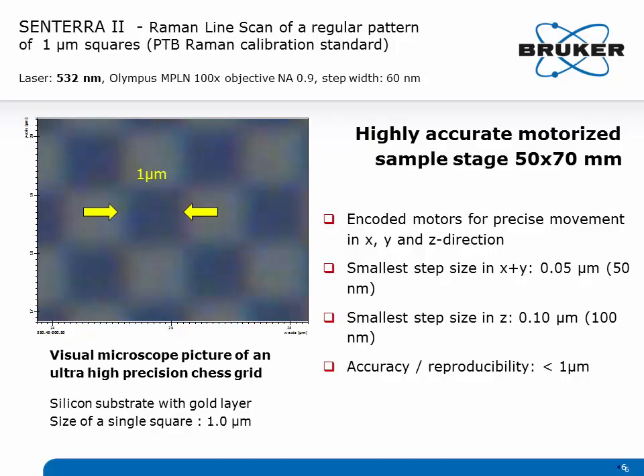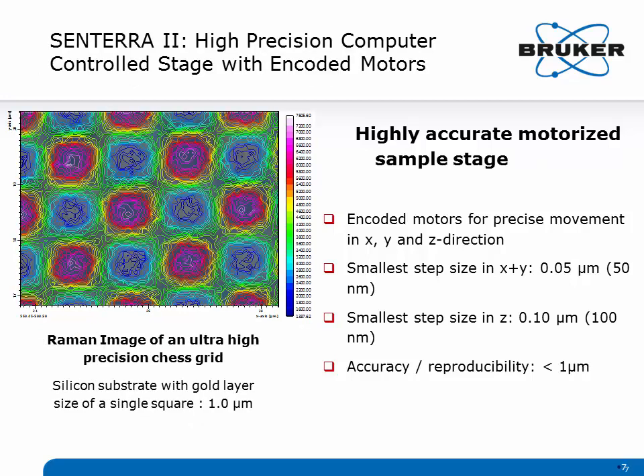To achieve this kind of precision, it's not only necessary to have a high-quality objective, but you also need a highly accurate motorized sample stage. The SENTERRA II features encoded motors for precise movement in all three directions. The smallest step size in X and Y is 50 nm and the smallest step size in Z is 100 nm. The accuracy and reproducibility of the sample stage is defined as better than 1 µm, but as you can already see from the chemical image above, the accuracy is way higher than this.